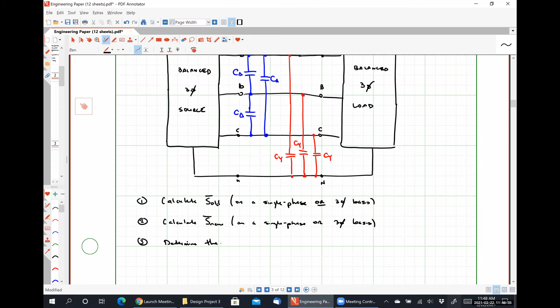Thirdly, we need to determine the VARs supplied by our capacitor, and this can only be done on a single-phase basis. I make this point because mathematically you could solve, if you calculated the difference between S new and S old, you could apply the equation to get a capacitor value, but that would be one capacitor correcting all three phases of the system, which isn't how this works. There are three capacitors, each correcting the power factor of one phase. That's why step 3 has to be done on a single-phase basis.